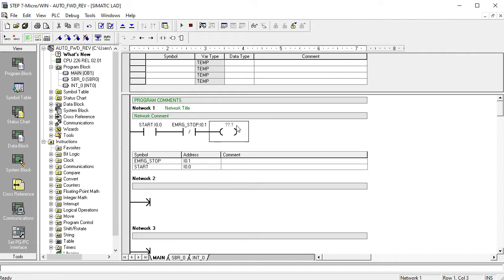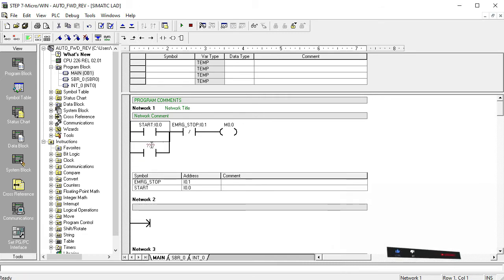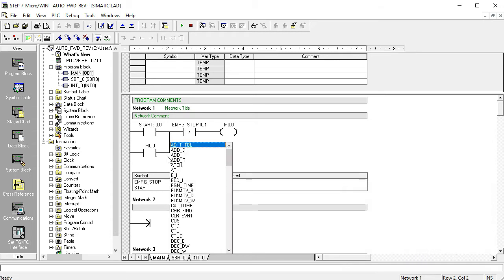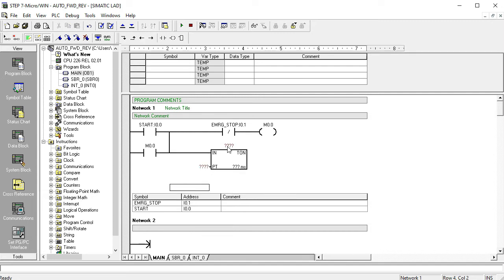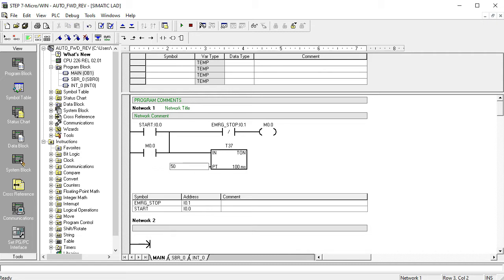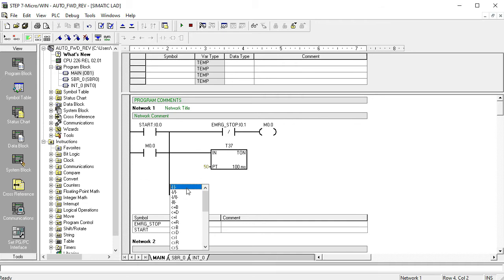When you write I0.1 for the emergency stop button, a break contact is shown here. I want to write M0.0 — this is a program memory bit. The program memory — simply don't introduce this to the main output yet, because this is not a main output. That's why I use M0.0. I want to delay my output, so I add a TON (on-delay timer) T37. As I described in a previous video, T37 is a 100-millisecond timer — 10 increments equals one second. For five seconds, the preset value is 50.